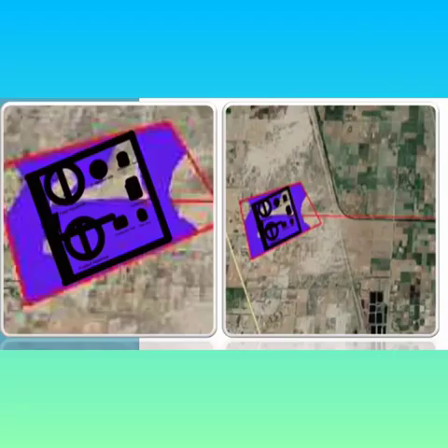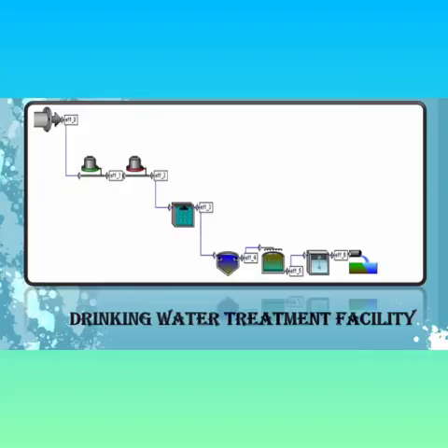Now this is the overall layout of the water treatment plant, in which the surface water treatment train components are present. This is the layout which we concluded using WaterPro software. Here is the overall summary from the software: the flow rate from effluent 01 to 06 is 3,15,512 meter cube per day, whereas the pH at effluent 01 you can note is 8, but at the last the pH reduced to 7.8.